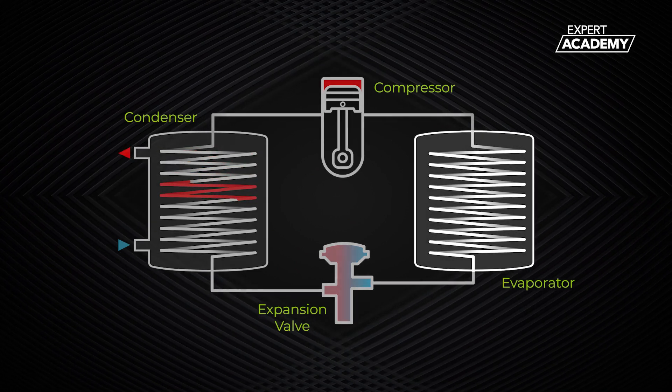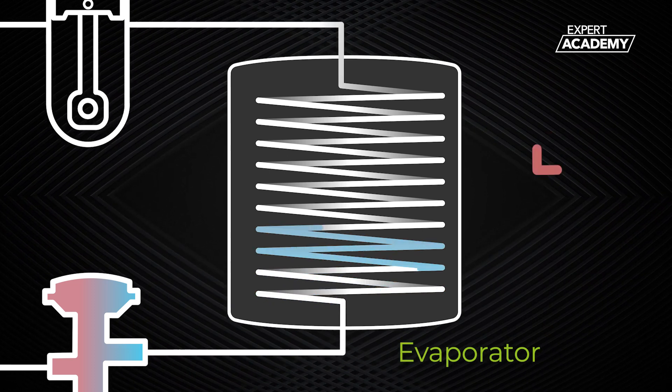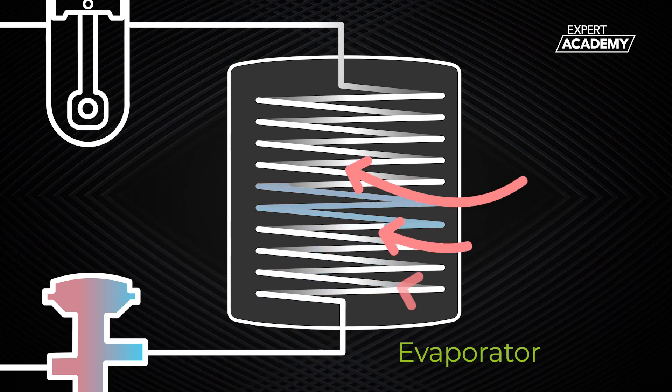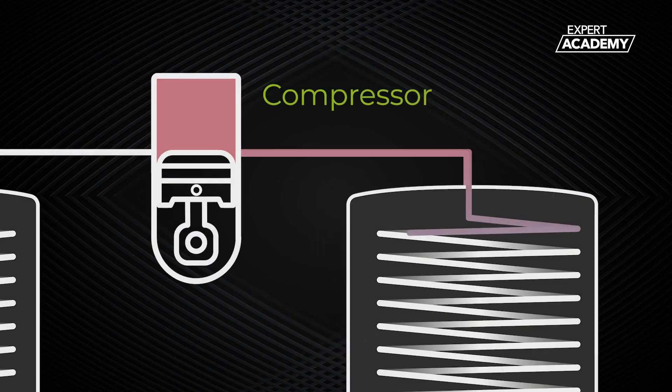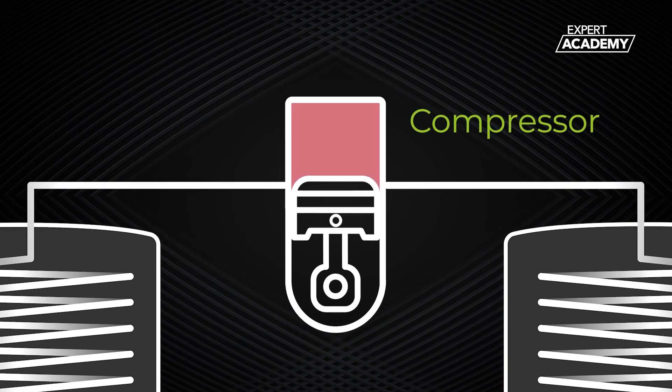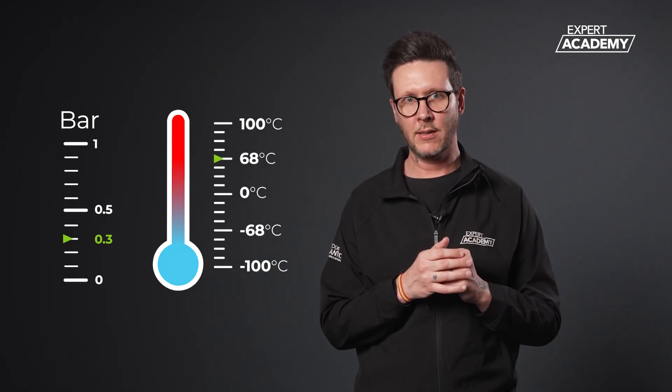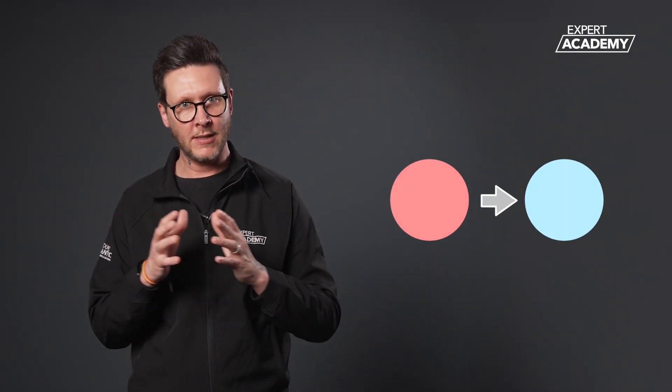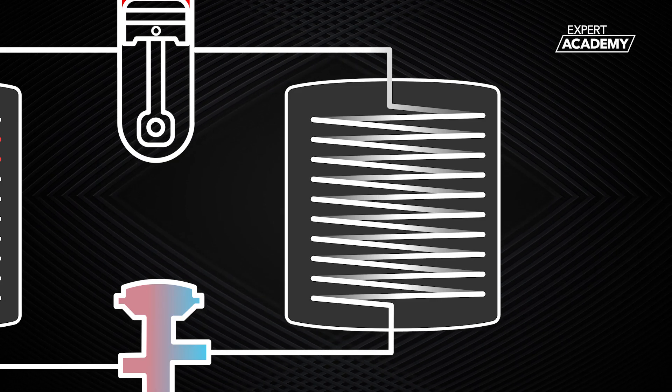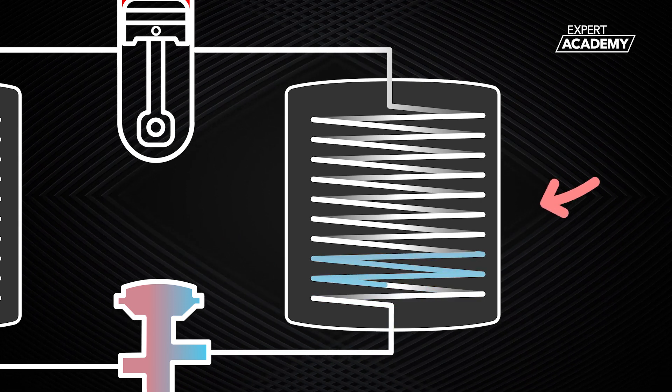We will start at the evaporator. At this stage of the vapor compression cycle, the refrigerant in the evaporator is at a far lower temperature than the surrounding outside air. It is also on the suction line into the compressor, which helps maintain a low pressure. Remembering that lower pressure reduces the boiling point of a liquid and heat moves from areas of higher temperature to areas of lower temperature. The greater the difference, the bigger the transfer.